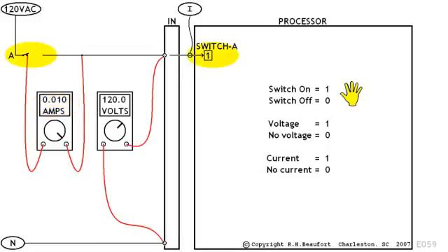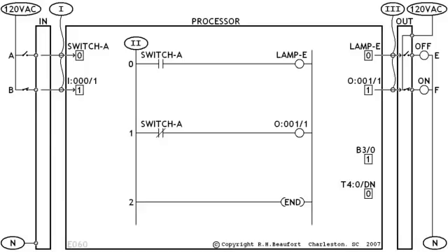Here we've fixed the broken wire, and now the on position of the switch does give us a 1 in the bit. Different input modules have different specifications for on and for off signals. The meter readings we're showing here are pretty typical for the type of hardware we're using for our video lessons. And here's where we stand so far.